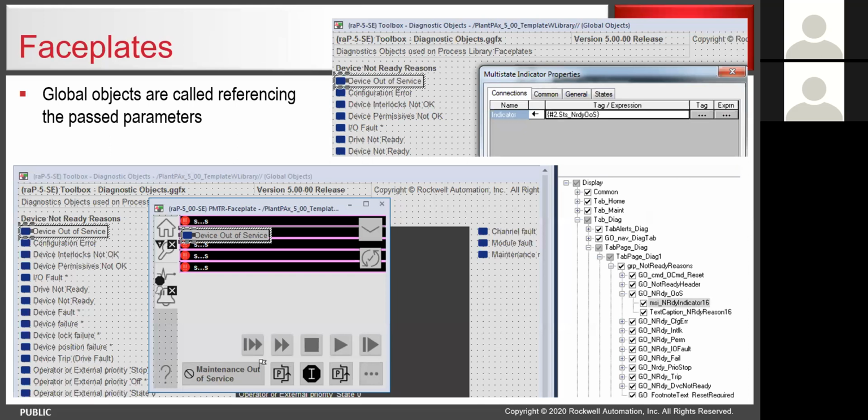On the SE side, we typically do a lot more with the security coming from the HMI. On the ME side, sometimes you'll see it in both the controller and the HMI, because you can typically only have one display running off of a controller. On the SE side, we're typically running multiple displays off of one controller. So the controller can't really manage who's seeing what, because you could have multiple people with different credentials logged in at the same time.